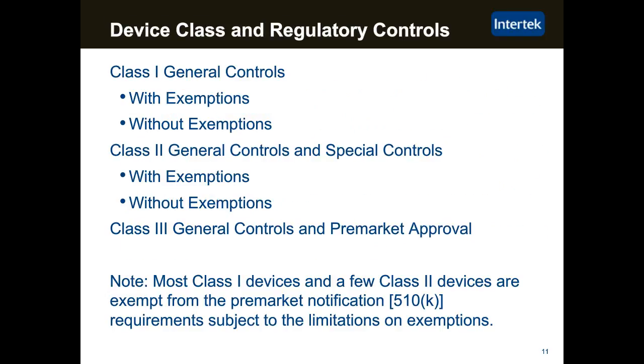So in terms of the different classes and regulatory controls, Class 1 devices are governed by general controls. And general controls are your basic provisions that were set out in the 1976 Medical Device Amendment legislation that provide the FDA with a means of regulating the devices to ensure that they're safe and effective. The general controls in the amendments apply to all medical devices. But in the case of a Class 1 device, it's really limited to those general controls. And general controls include provisions to avoid adulteration of products, avoid misbranding. It controls device registration and listing, pre-market notification, and many other areas of the regulations.